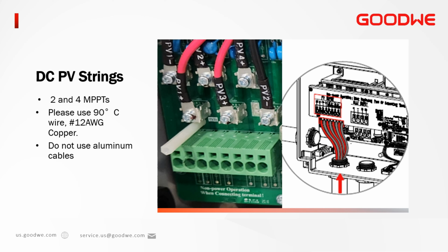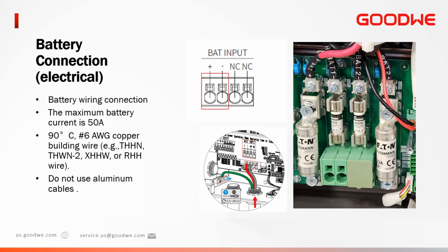As I mentioned earlier, don't forget to crimp the PV terminals to the wires. Please make sure to validate string voltage and polarity. Although the inverter has reverse polarity protection, it is always best practice to check before installing. Now let's move into the different battery connections. But remember that this inverter is what we call battery ready, which means that you might be commissioning this inverter without battery. If you are using the AES inverter as PV only, then skip this part of the connection.